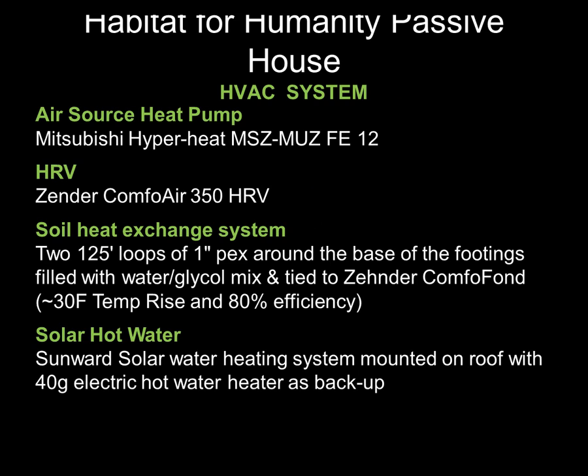The HVAC system for this house, even though most of the energy provided is through passive means, we do in northern Vermont need some kind of actual heating system for the house. And that system for this building was a Mitsubishi Hyperheat air source heat pump with a design load of about 12,000 BTUs per hour. Very, very low load building, so it required a very small amount of equipment. We also had the heat recovery ventilator I'd mentioned and the solar hot water system.